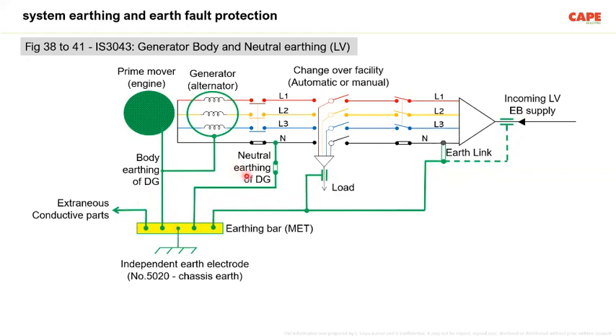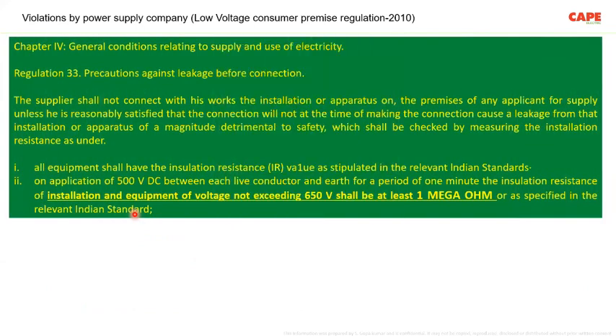So this is the correct way of earthing. This means different metallic exposed and extraneous conductive parts in your building must have interconnection, not under the soil, but above the soil, a physical connection. So this is the correct way of earthing.